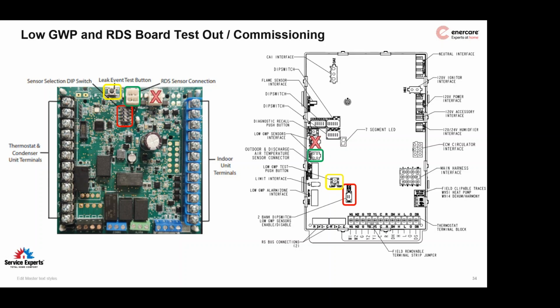Once you've validated that the outdoor unit did in fact shut off and the blower continued to run to dissipate, on the board you'll see a leak. It'll be in leak test procedure. On the 7-segment display on the board on the right, it will show you that it's in a leak mitigation error code, and we'll see a list of error codes shortly for that board specifically. Once you've confirmed that it's shut off, simply push that test button one more time, and what it'll do is take it out of that test mode and go right back to its normal operation. And you've validated the cooling function: that if there was ever a leak during cooling, that leak mitigation process will happen.